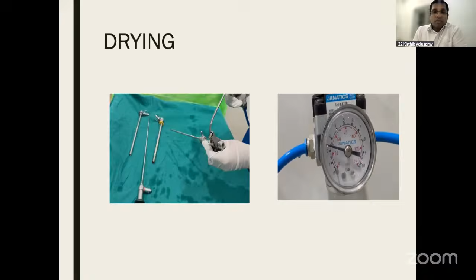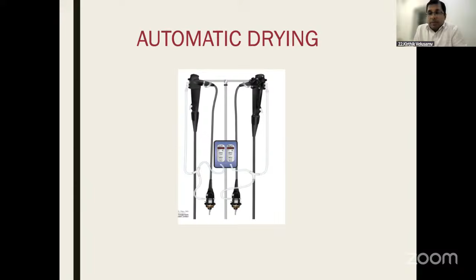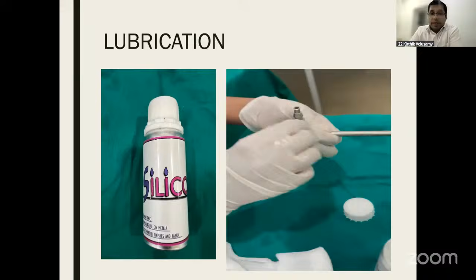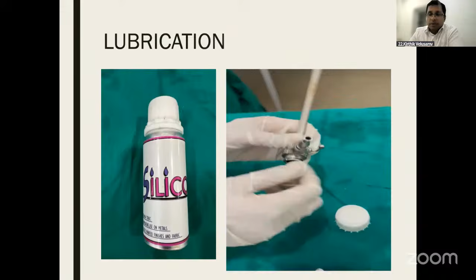Automatic drying is available in some centers, where once the scope gets rinsed, it is connected to tubings which are connected to the machine, which will dry it automatically. Once drying is done, if the opening and closing tap of some scopes is very tight, we tend to use a silicone lubricant. It is also used for any hinges or scissors, or any laparoscopic scissors, for lubrication.